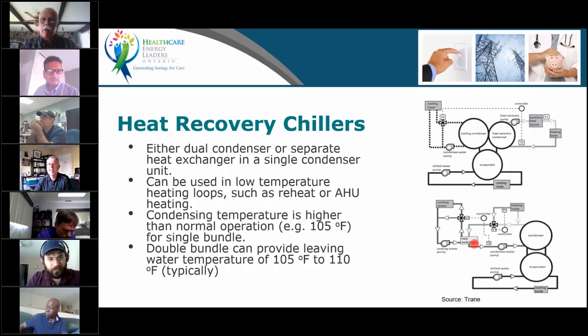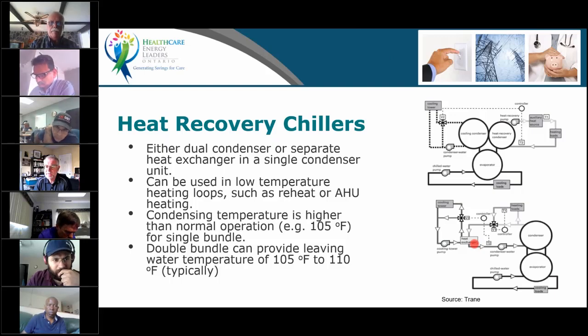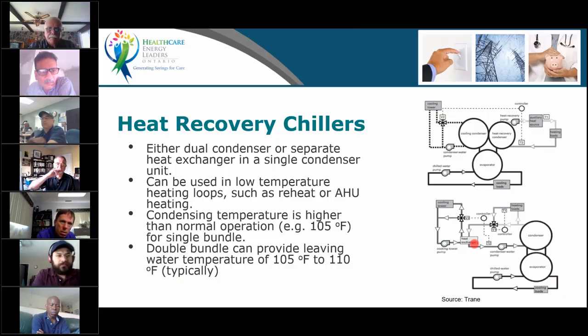So I would encourage you to use your heat reclaim chiller to satisfy your low temp heating requirements, like your reheat and preheating domestic water and some of your air handlers, and then use your cogen to satisfy your high temp heating requirements, like the building radiation, the steam for medical processing, all your autoclaves, all that. So if you can, because a cogen will make higher grade heat than a chiller will, knock the low grade heating off with the chiller. Use the CHP for the high grade heating requirements.